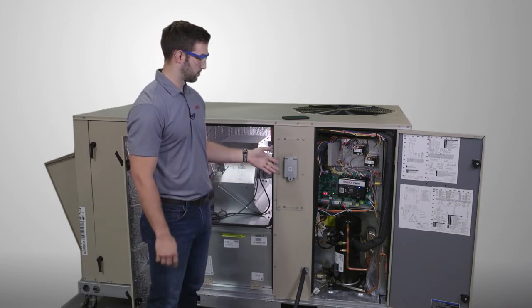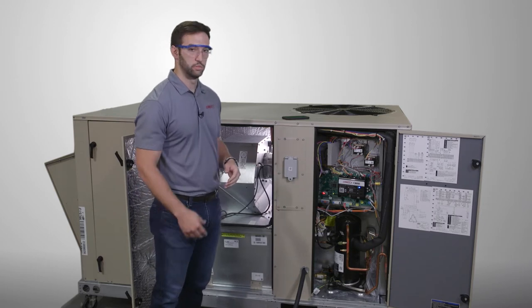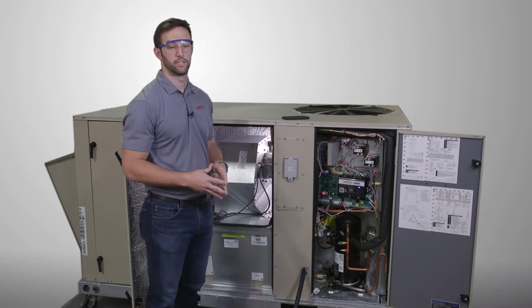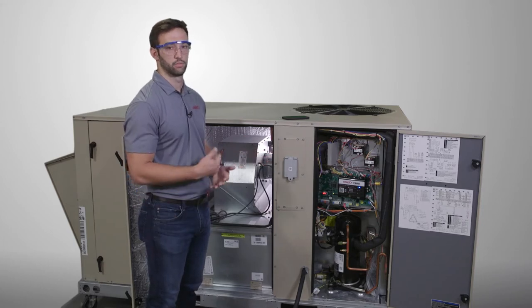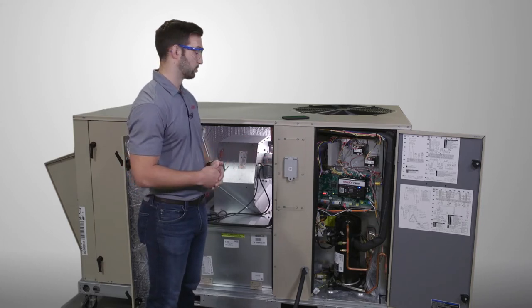For our variable speed compressor, it is going to be modulating based on the dehumidification demand in space. The further you are away from set point, the faster that compressor will run to remove more moisture from the air.